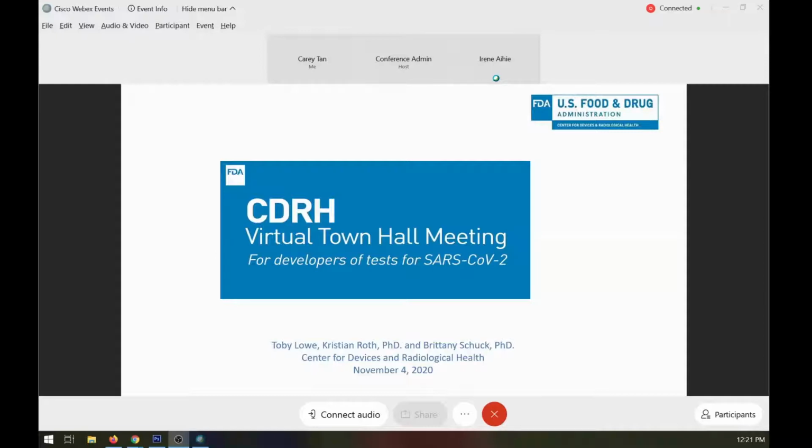My question is, if we have an EUA-approved molecular test, say approved for nasal swabs, and we wanted to change the sample collection part of that and use saliva collection that was approved, how should we go about that? Do we have to send in a brand new EUA, or is there some type of bridging study, or do we do a verification study?